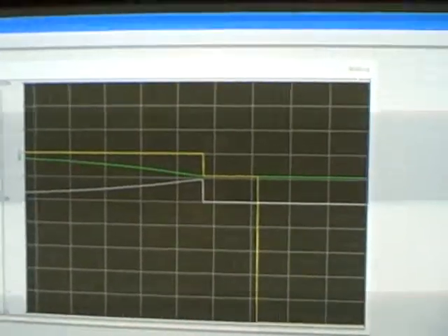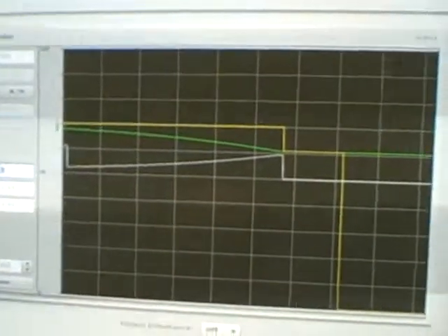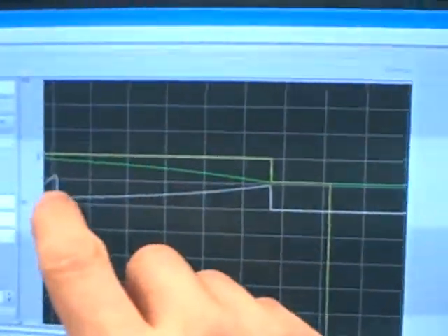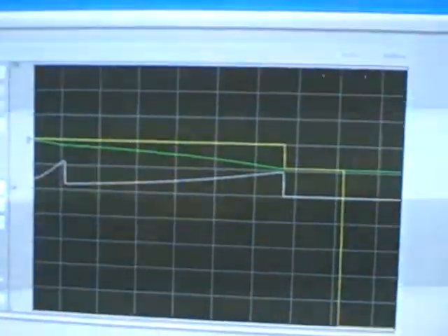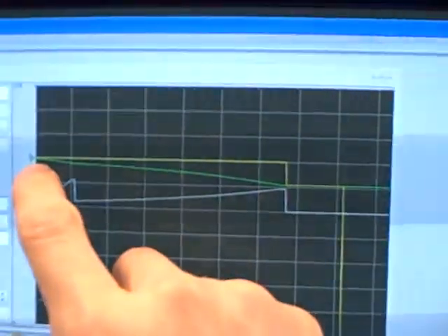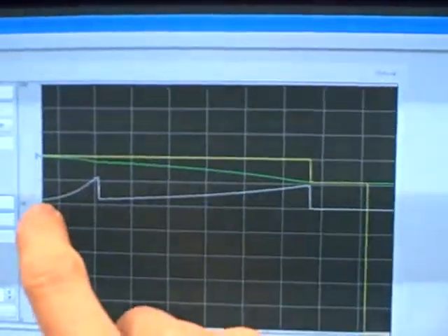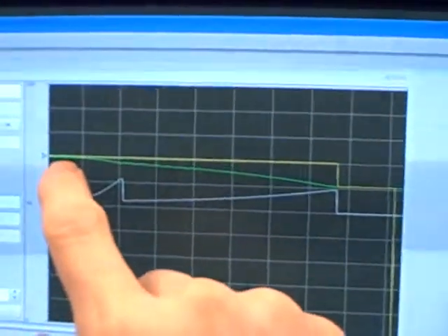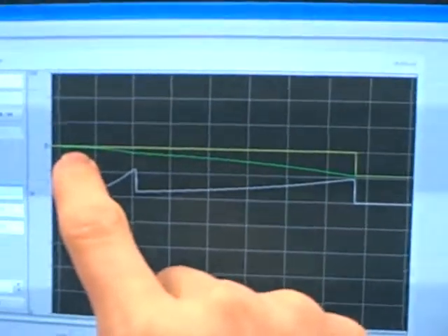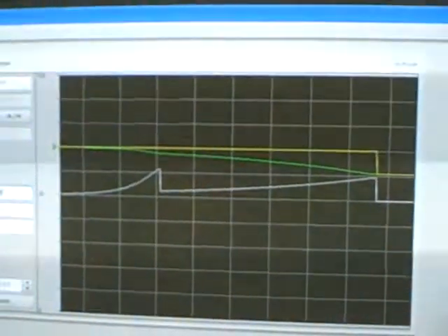So I'm going to take my gain value and go to a gain of 5. 5 times more aggressive than what we have right now. I'll enter the new gain value. We see the valve step up even more, and then the process variable approaches set point at a much more rapid pace. And notice as it does, as the PV achieves the new set point value, our valve position goes back to pretty much where it started at, around 50%. And it will remain at set point there because this is an integrating process, and it's happy to hold level when we move our valve back to its original position.